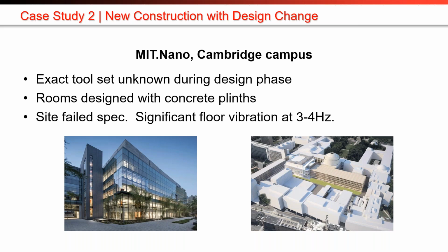But the unknown tool set means unknown vibration criteria. So the team wanted each tool owner to be able to choose their own preferred vibration isolation method. So they designed the facility with plinths and pockets so that each tool owner could put whatever isolation under the plinths that they wanted. So that was the plan.